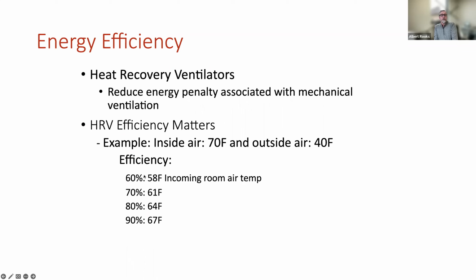Really, the simple thing are those 4 numbers at the bottom of this slide. So if we went to the store and we bought an HRV that was 60% effective, and we look at the labeling, and the lowest, most conservative number that we see is 60% effectiveness. If we put it in a home that's 70 degrees inside, and 40 degrees outside, essentially what's going to happen is we'll bring in that 40-degree air and we'll recover the heat from that 70-degree flow. And at 60% efficiency, that means the supply flow that's going to typically show up into the master bedroom or the public areas where people tend to live, it's going to be 58 degrees.